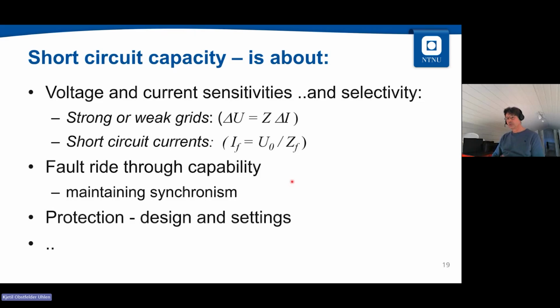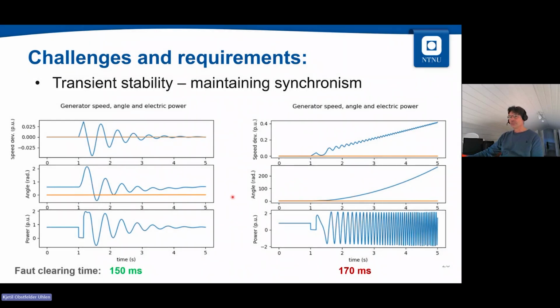So that impacts what we call the fault ride-through capability of the machine, their ability to maintain synchronism when there is a fault. And consequently, it also affects the protection and design of settings of the protection. So just some examples I used to show in my lectures. Here you have one generator connected to a grid, a 40 megawatt generator. You have a three-phase short circuit cleared after 150 milliseconds, and you see you got the power swings, but it remains stable. If I delay the clearing to 170 milliseconds, you lose synchronism.